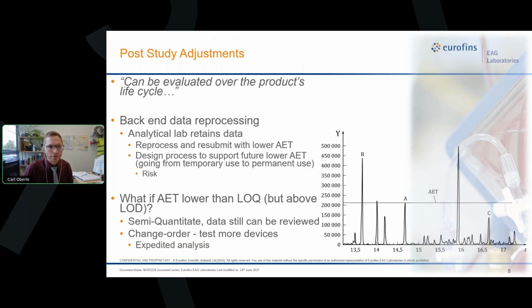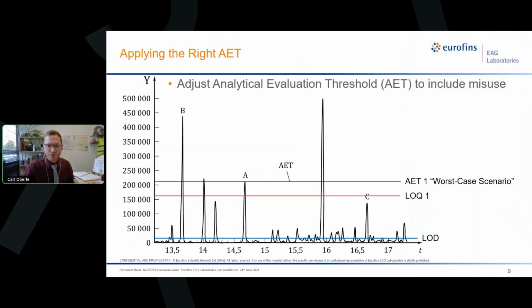Now, certainly, the last case scenario would be getting a change order, sending more devices to the testing facility with that lowered AET. So I have a bit of an interactive graphic here to demonstrate what I meant with the AET and the LOQ. If you look at the first case scenario, where the AET, we're calling it AET1 here, is just the worst case scenario that includes worst case extracts, high temperatures, cycles, etc. And that LOQ is set accordingly, just below the AET.